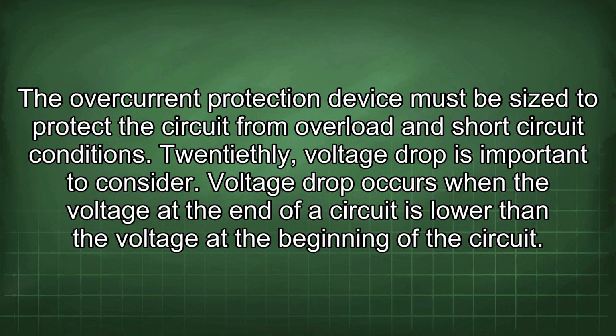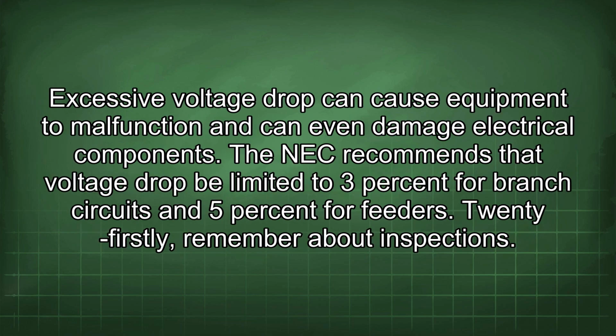20thly, voltage drop is important to consider. Voltage drop occurs when the voltage at the end of a circuit is lower than the voltage at the beginning of the circuit. Excessive voltage drop can cause equipment to malfunction and can even damage electrical components. The NEC recommends that voltage drop be limited to 3% for branch circuits and 5% for feeders.